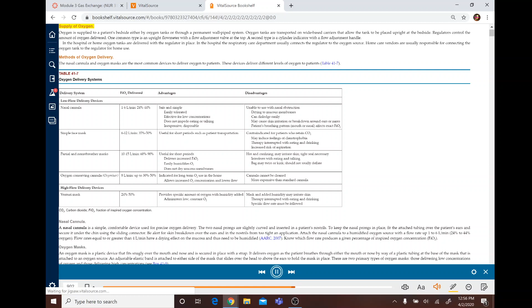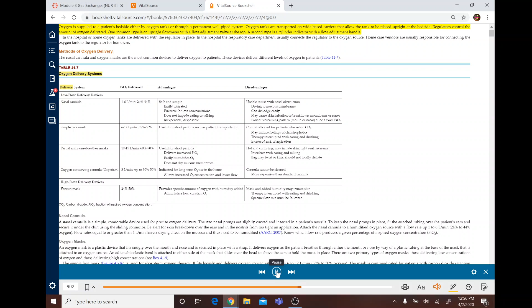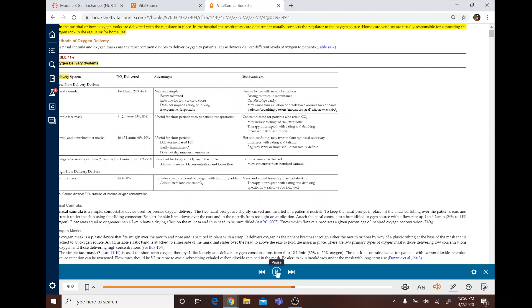Supply of oxygen. Oxygen is supplied to a patient's bedside either by oxygen tanks or through a permanent wall pipe system. Oxygen tanks are transported on wide-based carriers that allow the tank to be placed upright at the bedside. Regulators control the amount of oxygen delivered. One common type is an upright flow meter with a flow adjustment valve at the top. A second type is a cylinder indicator with a flow adjustment handle. In the hospital or home, oxygen tanks are delivered with the regulator in place. In the hospital, the respiratory care department usually connects the regulator to the oxygen source. Home care vendors are usually responsible for connecting the oxygen tank to the regulator for home use.